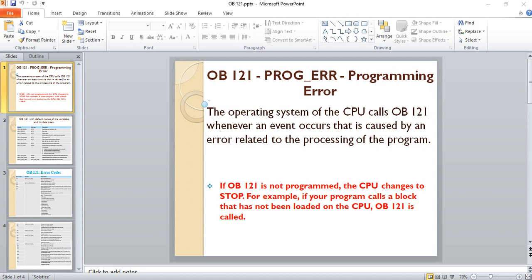If OB-121 is not programmed, the CPU changes to stop mode. For example, if your program calls a block that has not been loaded on the CPU, OB-121 is called.